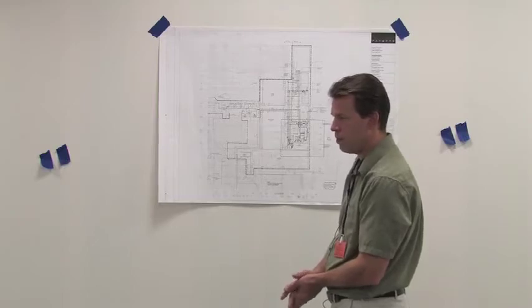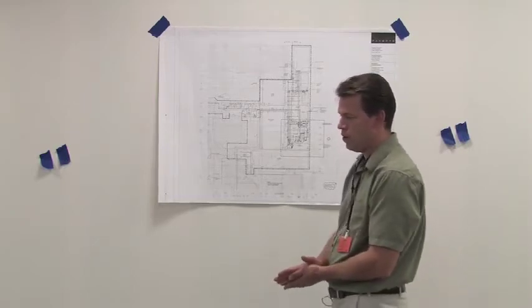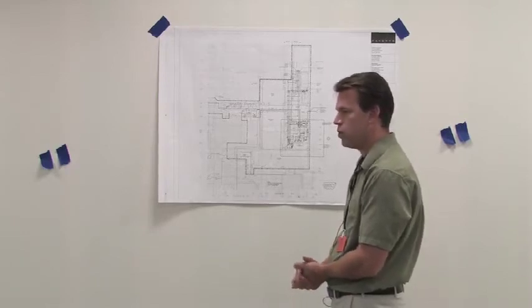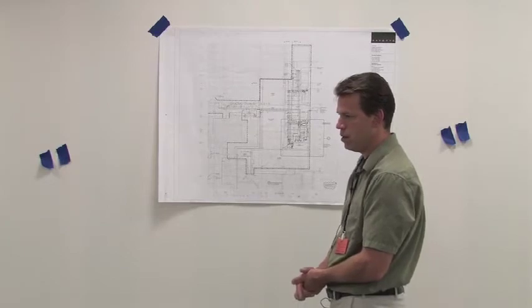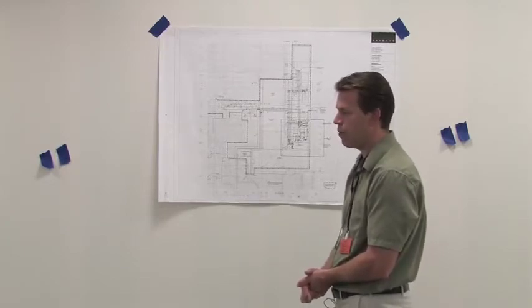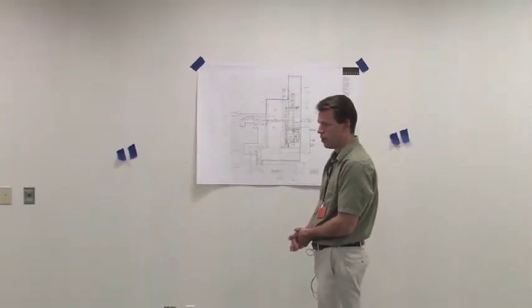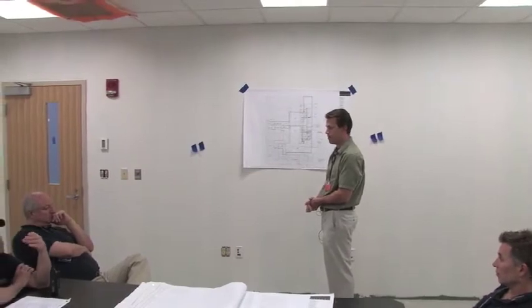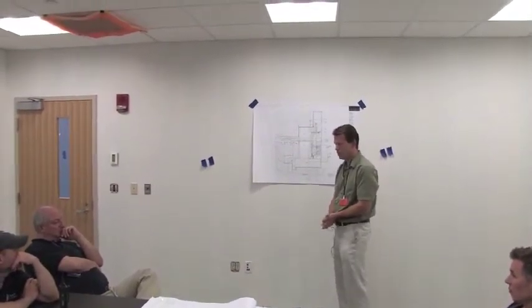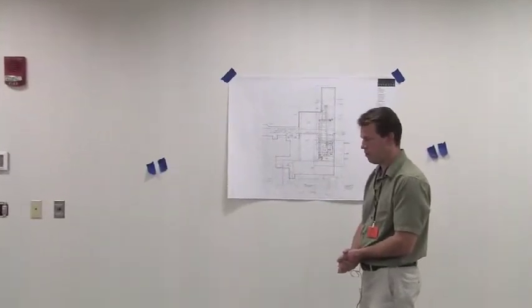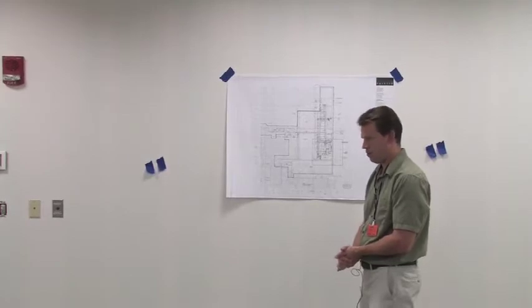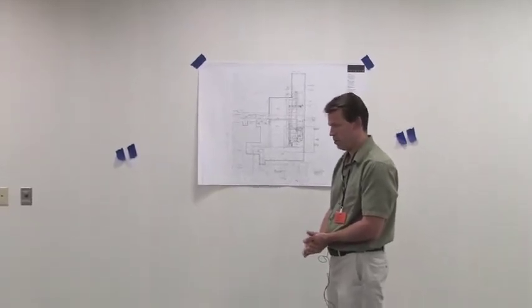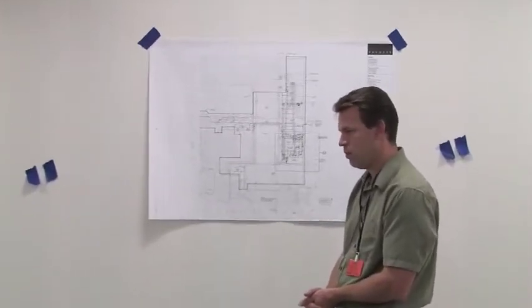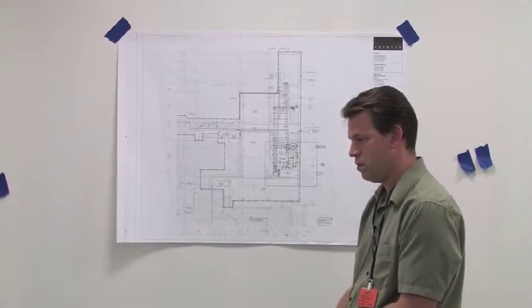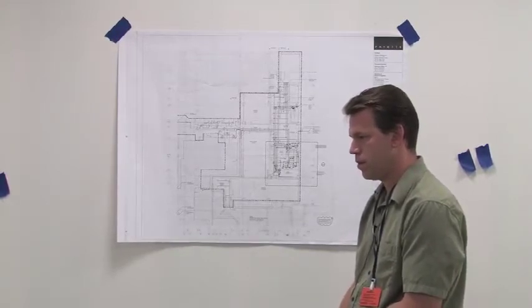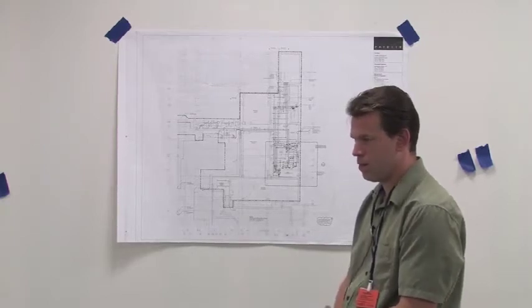And is that compressor just dedicated to that? That compressor serves the dry pipe for the ambulance bay as well as the pre-actions on 2 and 7 for the MRI spaces. So that's plumbed all the way up to the MRI spaces? Correct. There's a compressed air riser going up in the plumbing closet and that branches out and feeds. So there are no smaller compressors at those locations? No. You just have that central air? Correct. That goes to all the dry and the pre-actions, the MRIs, with all the bells and whistles, pressure switches and all that stuff at those locations. Exactly. A separate pre-action closet on the second and a separate pre-action on the seventh. Little closets with those valves. No noise in them, because there's no compressed air. Right.